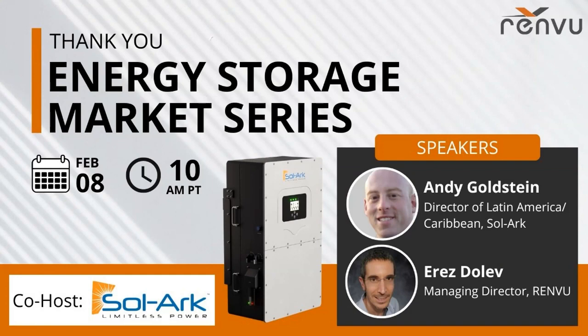Does the 30 and 60K have UL9540 with which batteries? Right now, all of our battery partners are currently in the UL 9540 process. It seems there continues to be confusion in the market about UL 9540 — people think this is an inverter certification. It is not; it's a battery certification. They have to take our inverter to get the UL 9540. So we kindly ask you reach out to battery companies for their feedback, because they're the ones driving that certification. We will prioritize their needs 100% from our side, but it's up to the battery manufacturers to get this accomplished.